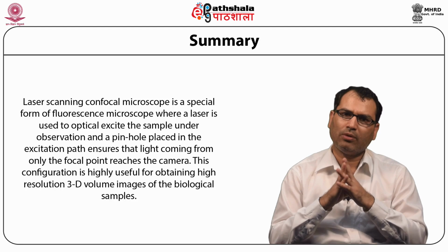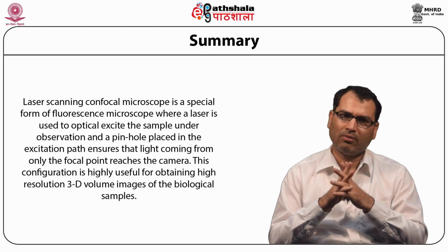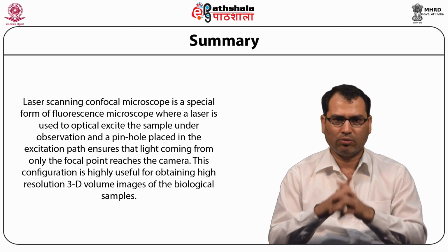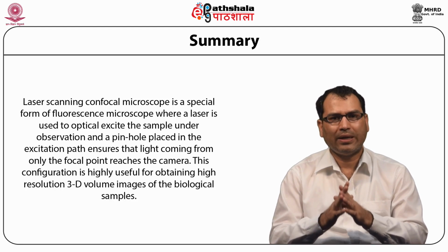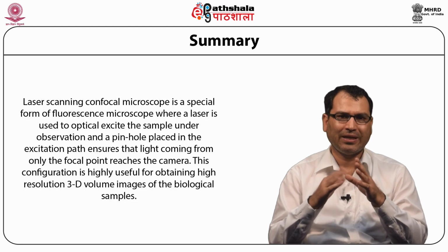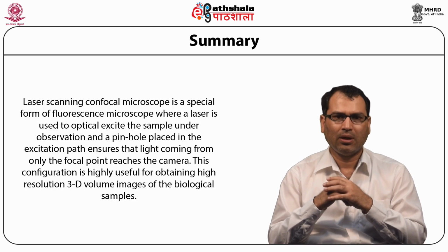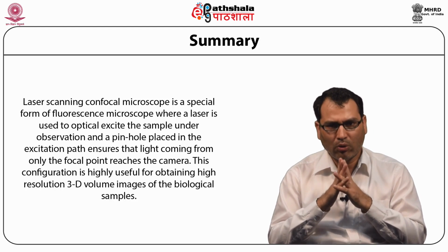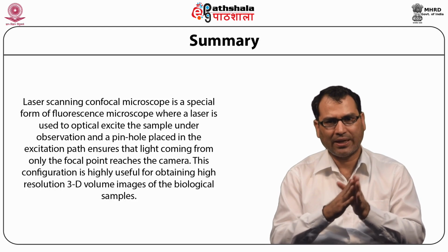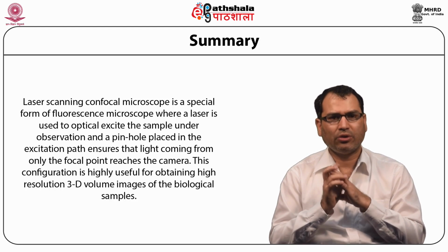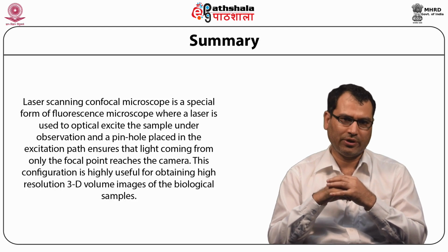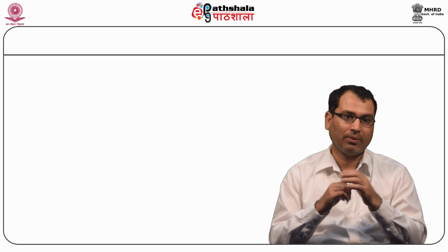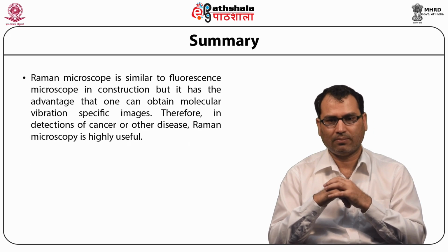Laser scanning confocal microscope is a special form of fluorescence microscope, where a laser is used to optically excite the sample under observation, and a pinhole placed in the path ensures that light coming from only the focal point region within the sample reaches the camera.